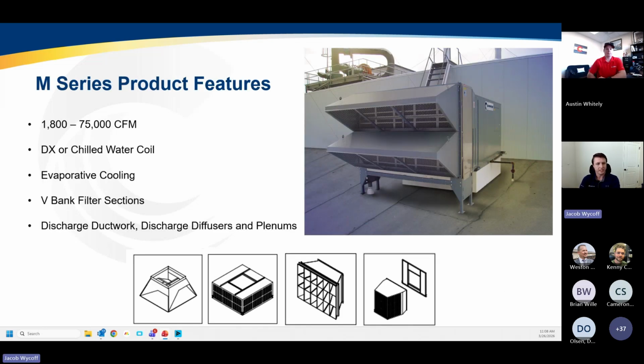Some of the key product features that we have, airflow ranges from 1800 to 75,000 CFM. We also offer bolt-on DX or chilled water coil sections that would be mounted upstream of the unit. The condensing unit or the chilled water supply would have to be provided by others, but this allows them to get cooling in a single package. We also work with A2L refrigerants for our DX coil, so we'll provide the refrigerant detection system and the refrigerant mitigation sequences as well to allow for compliance with the codes. We also offer evaporative cooling.